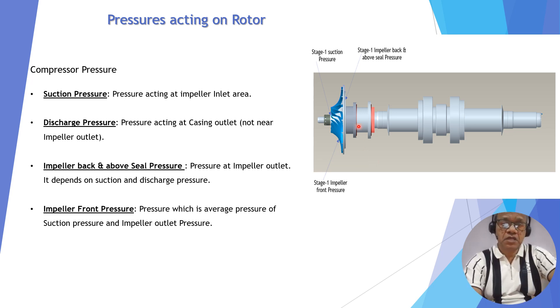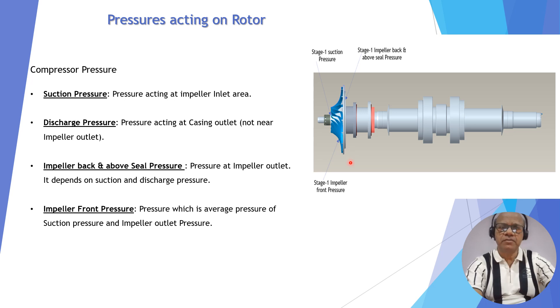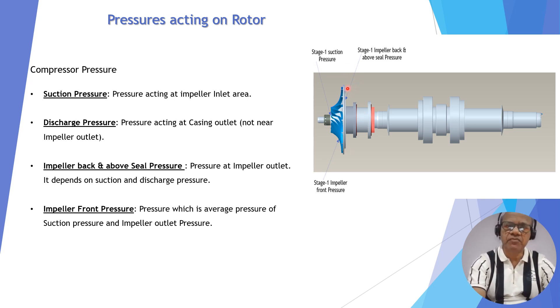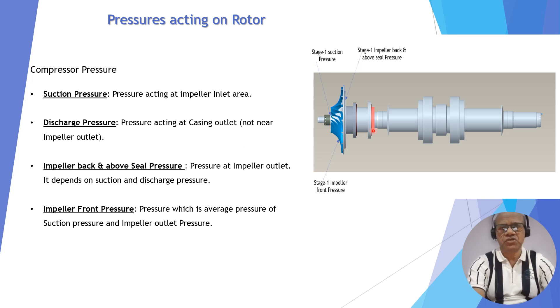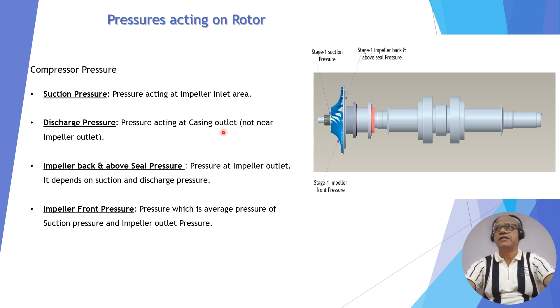The rotor thrust is taken care by the axial bearing. Looking at the impeller back side, there is a wheel seal that divides the back area into two sections: a portion above the wheel seal and a portion below the wheel seal. In a compressor, both the pressure above and below the wheel seal are the same, so in calculation we consider one combined back pressure covering the total area minus the shaft area. This is the impeller back-and-above-seal pressure. There is also the impeller front pressure, which is the curved area pressure acting on the front face of the impeller.